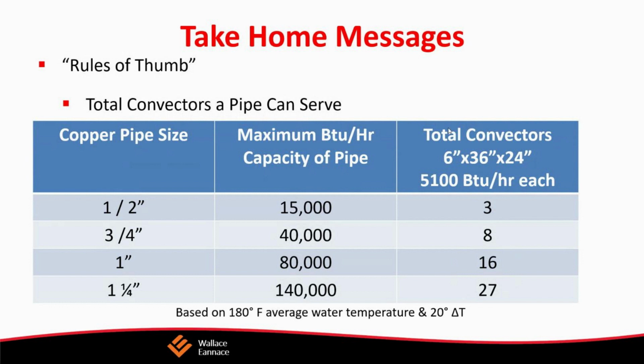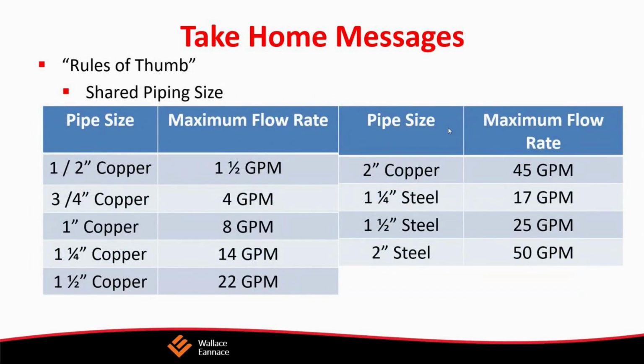The maximum flow rate and heat carrying capacity. So at a 20-degree delta T, the most heat that you can get through a half-inch pipe is 15,000 BTUs, and 40,000 BTUs through 3/4 inch pipe. If you're doing residential work, that's a really important number to remember: 3/4 inch pipe, 40,000 BTUs. If I have more than 40,000 BTUs, I need to set another branch or another zone out. 1 inch pipe, 80,000 BTUs, and 1 1/4 inches is 140,000.